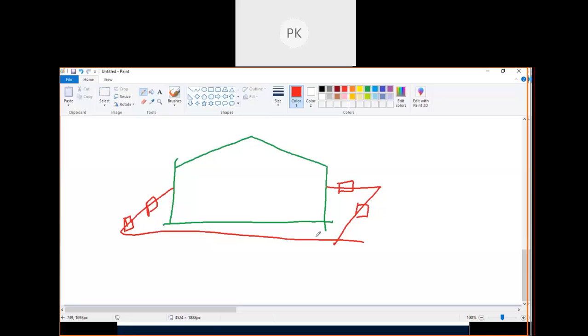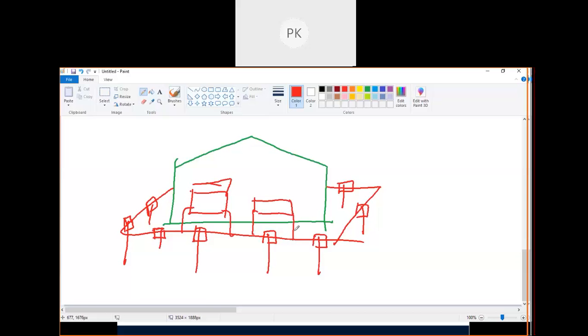How many earth pits are required, I will teach you during this training. I have to determine how many earth pits are required, and these earth pits are what you call vertical driven rods also. Now, let's say inside this you have some panel, some motor. All these are interconnected to this. If this is a metal roof, and I'm having a lightning conductor here, that drops down vertically and will have a dedicated earth pit, which will be interconnected to this earth pit.